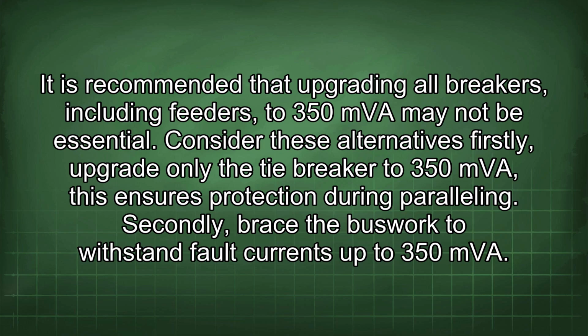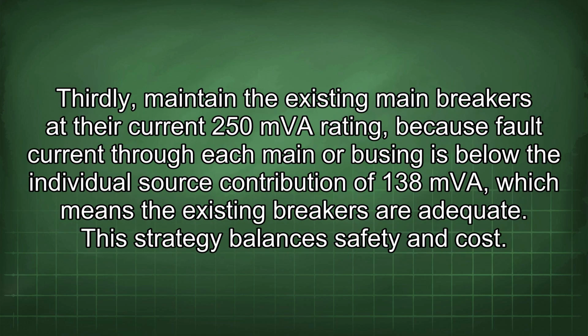Consider these alternatives. Firstly, upgrade only the tie breaker to 350 MVA. This ensures protection during paralleling. Secondly, brace the buswork to withstand fault currents up to 350 MVA. Thirdly, maintain the existing main breakers at their current 250 MVA rating, because fault current through each main or busing is below the individual source contribution of 138 MVA, which means the existing breakers are adequate.